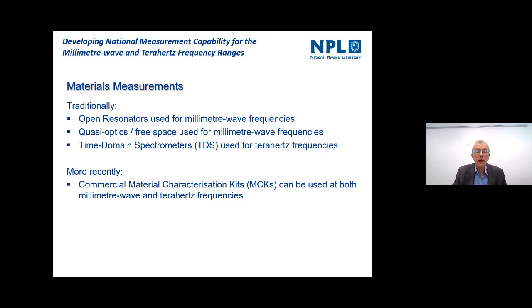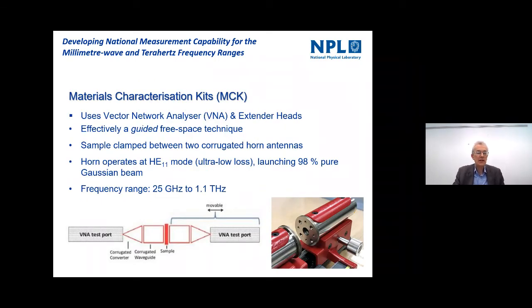So how do these materials characterization kits, MCKs, how do they work? Well, basically they rely on a network analyzer. They attach to the network analyzer extender heads that I showed you earlier. So at the end of the extender heads, we put one of these characterization kits, and they provide effectively a guided free space technique. In the bottom left there, you can see the 2 VNA test ports. Well, after that you have a horn section which uses a conical horn to launch the wave into a section of straight corrugated waveguide, which then launches this beam, a Gaussian beam for the materials measurement.